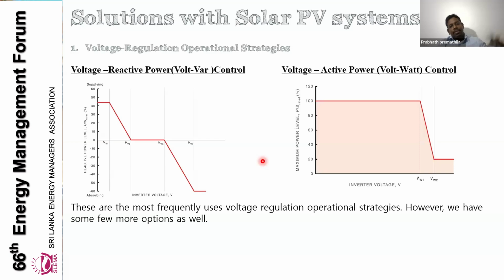If the voltage is low, we request the inverter to inject reactive power and come to the normal situation. In the active power case, we say if the voltage is beyond our permissible level, you have to curtail the active power and come to the normal operating voltage. These two are very famous, but unfortunately in the LV network we are yet to implement them. We have to implement these voltage regulation operation strategies as soon as possible. Not only these, but there are a few more options in addition.